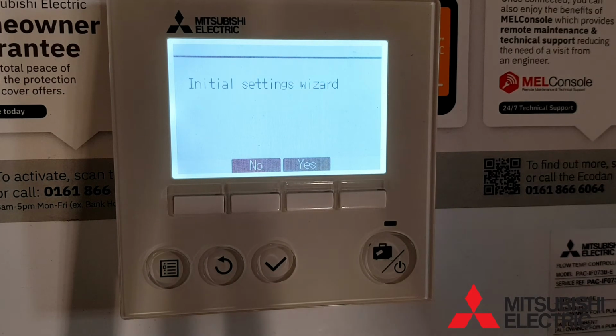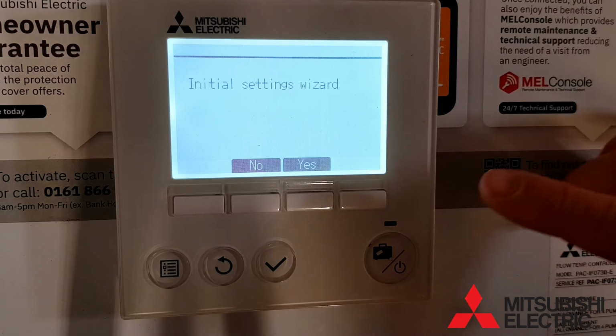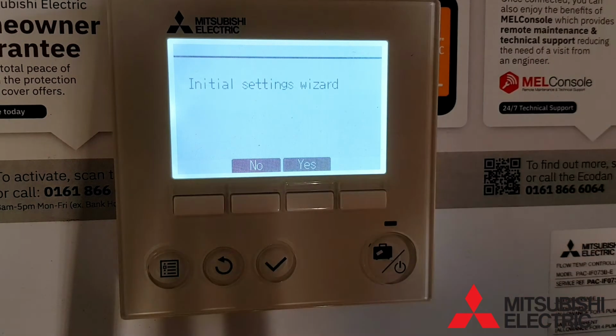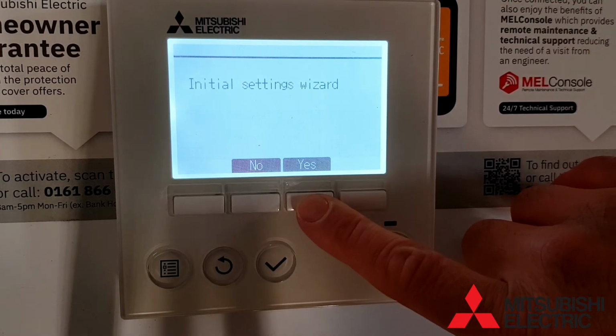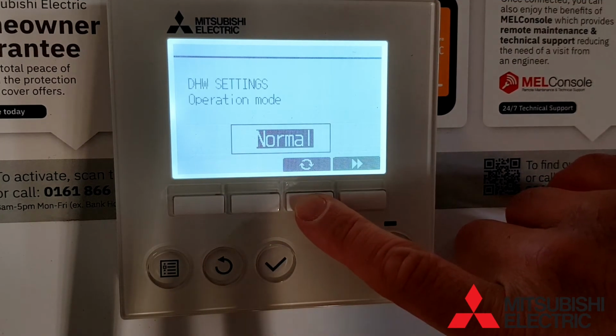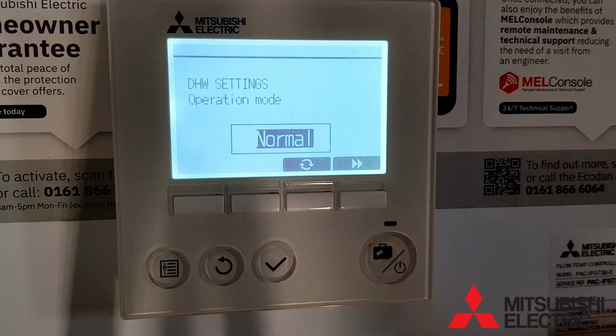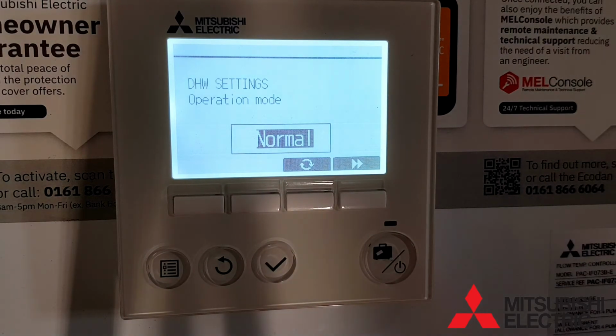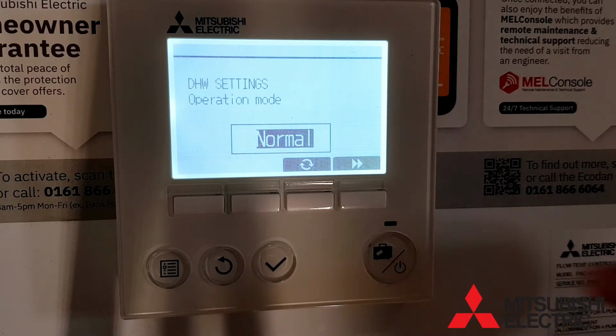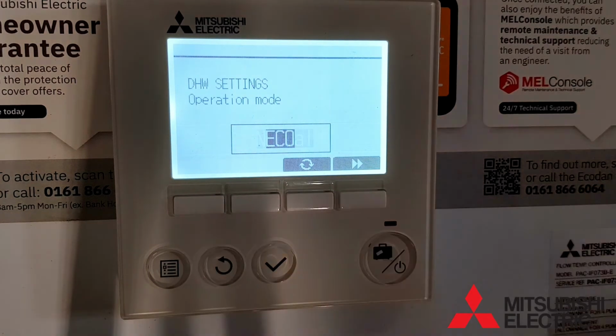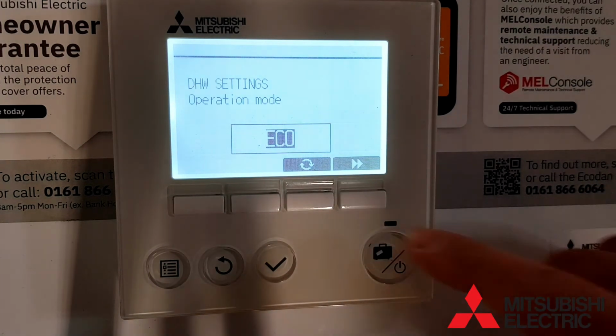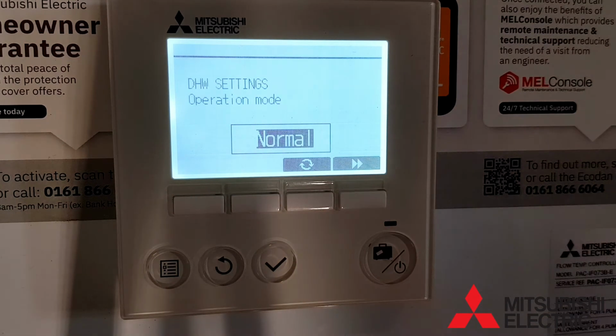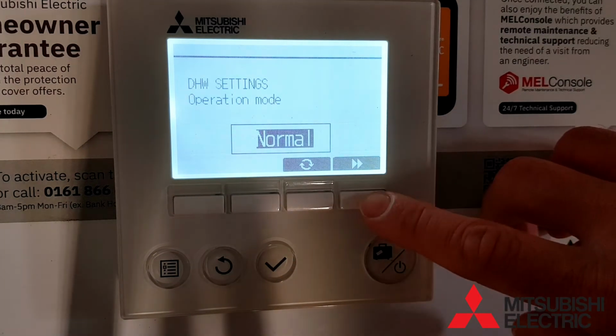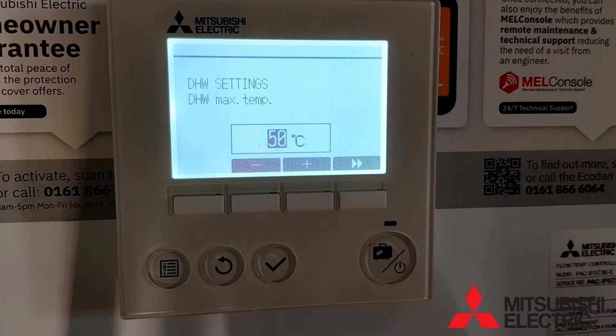When you first power up your Ecodan system, it will prompt you to use the Setup Wizard to program your commissioning settings. Select the Yes button to enter into the wizard. The first option is the hot water operation mode. You can run in normal mode, where it heats the cylinder as fast as possible, or eco mode, where it runs more economically, not allowing the inverter to ramp to its maximum speed. Press the forward button to move to the next screen.